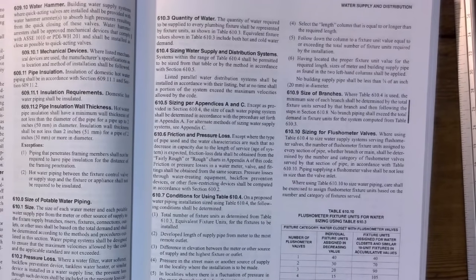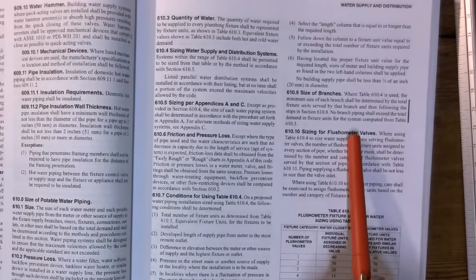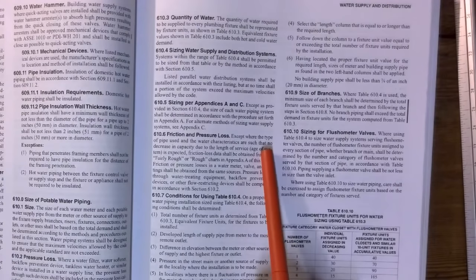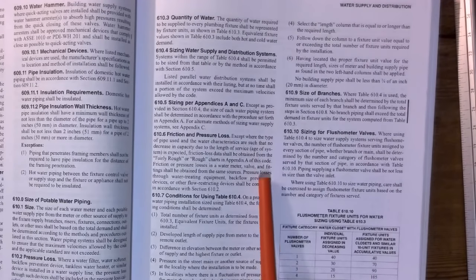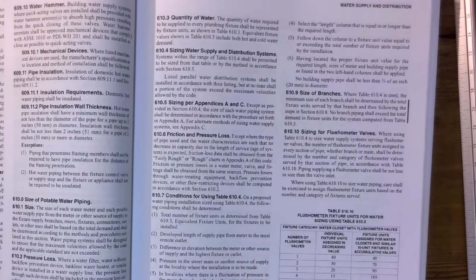So you follow down the column, you find a fixture unit value that is equal to or exceeding the total number of fixture units that are required for the installation. Then you go from that one and you run this way all the way over where it says size of meter, and that gives you the size of the meter. And then the other column on the right of that will give you the size of your building supply.